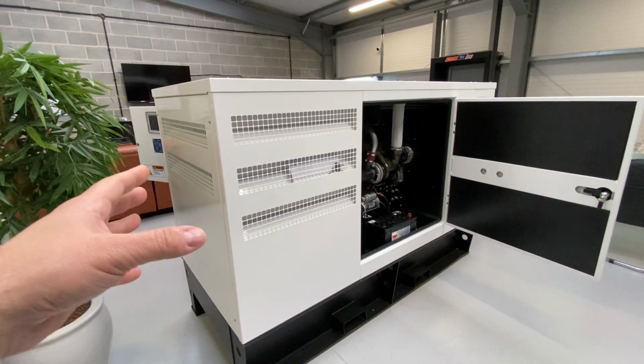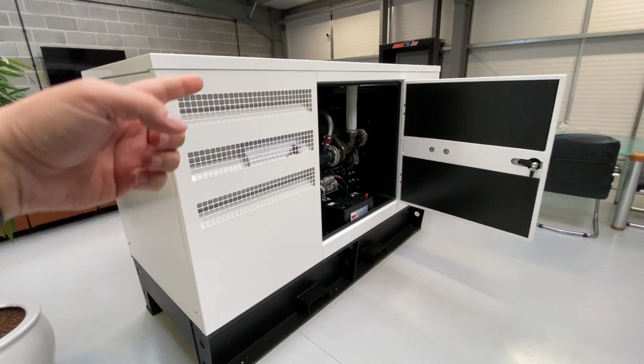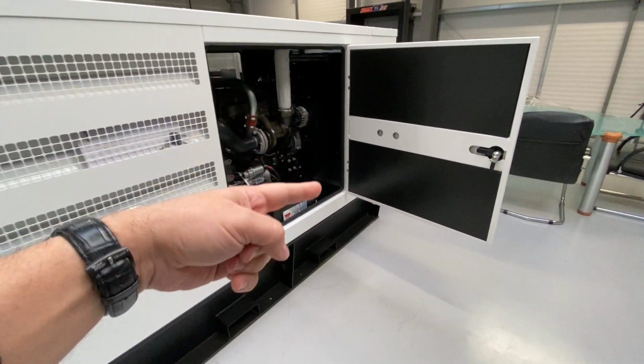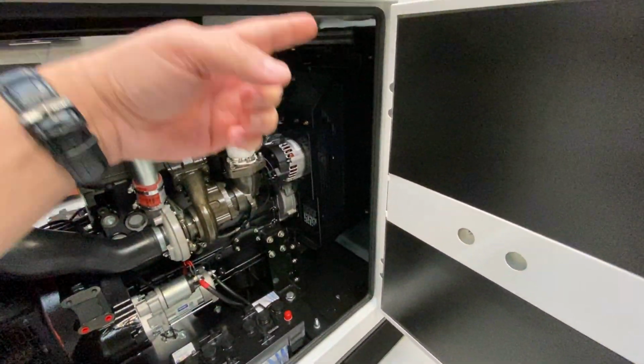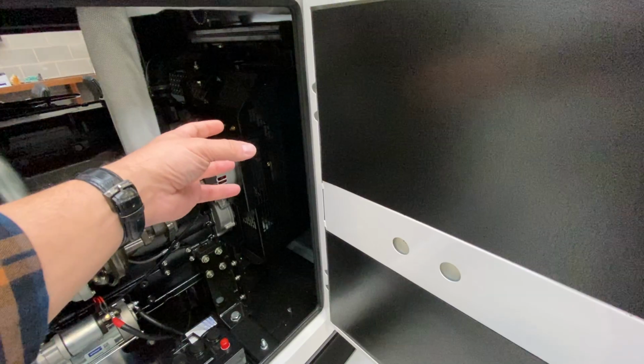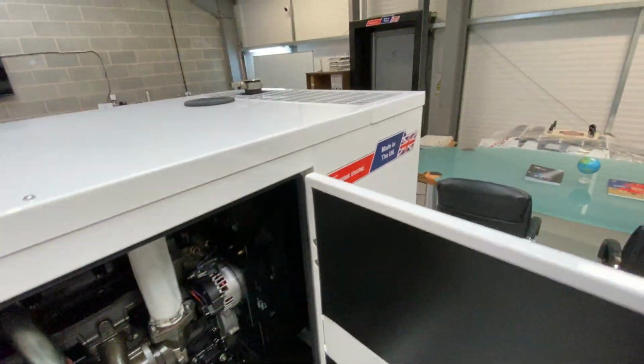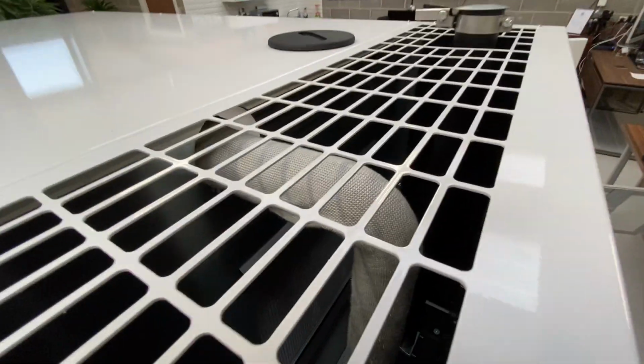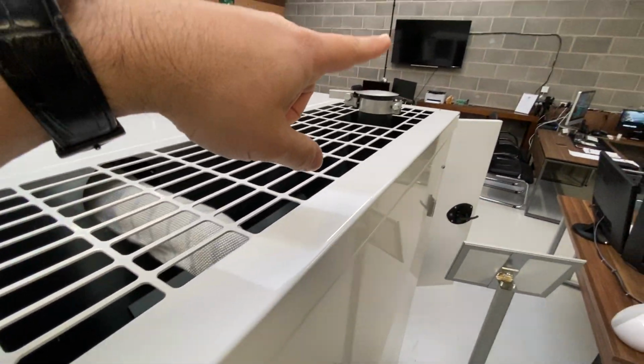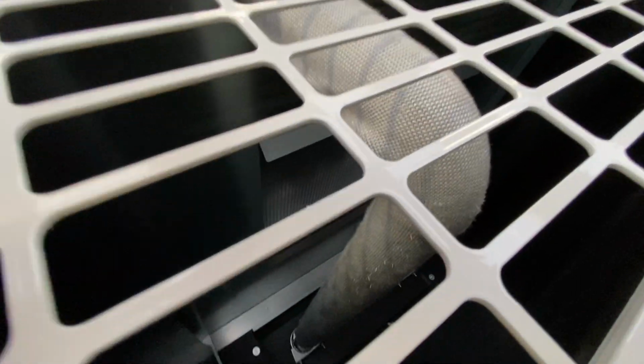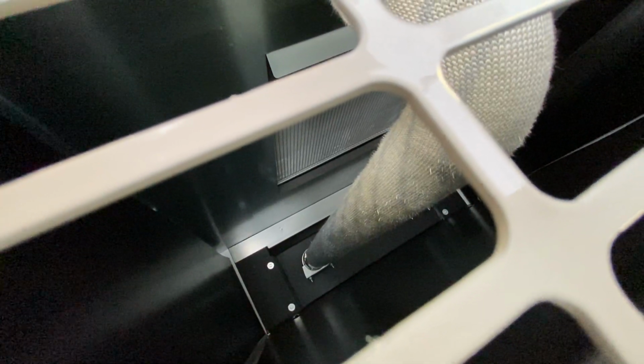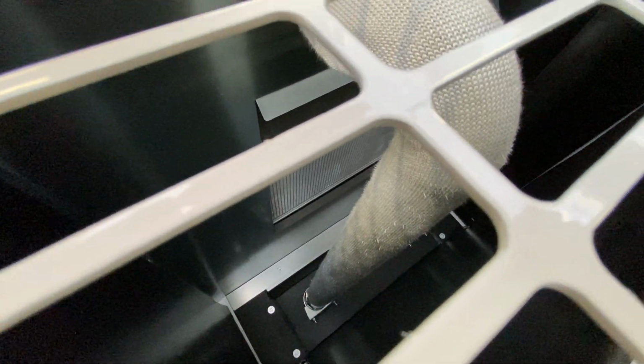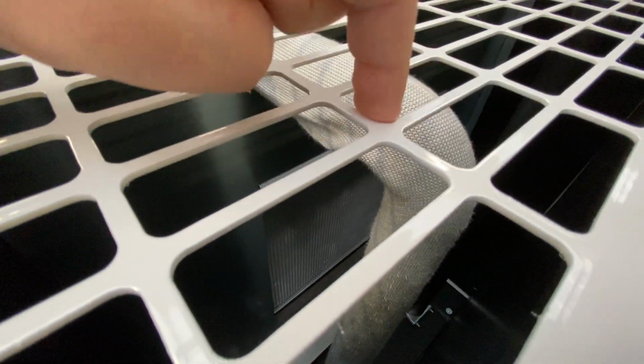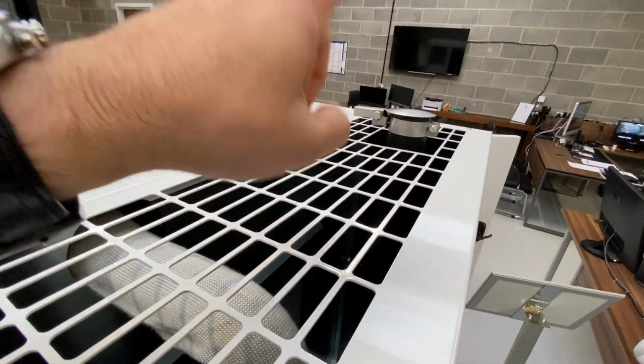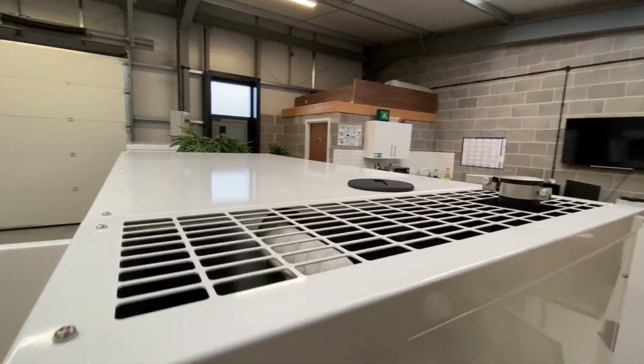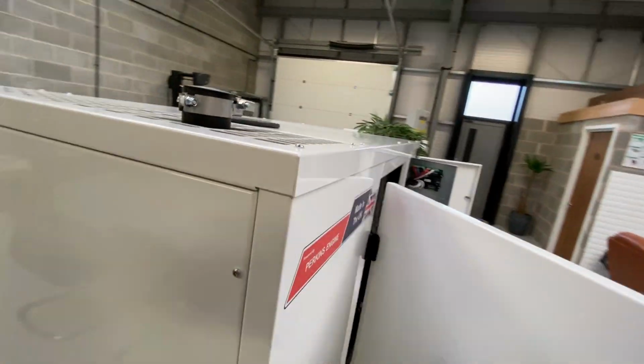Just to go through the canopy and the airflow—obviously it's sucked from behind and from the side, so it makes like a circular wave of air around the generator, pulled through the radiator fan, and then it's pushed upwards from the front through here and then pushed up with the fumes from the exhaust. The exhaust is actually in the bottom, integrated inside the base frame, and it goes down from here into the base frame, then goes from the other side, back up, and is pushed with the air high up, so you do not get fumes if it's in a tight space.